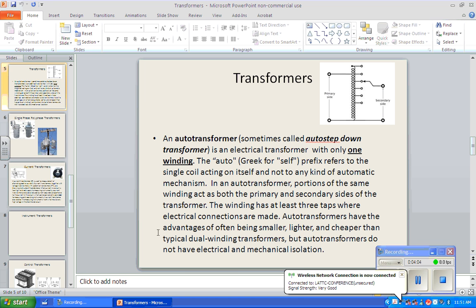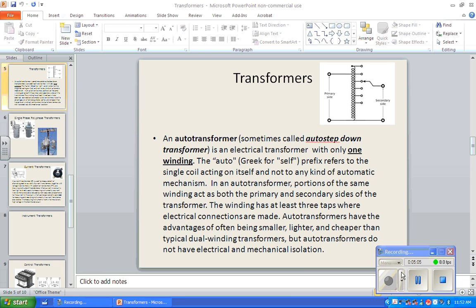Places where you will see in your future an auto transformer is at, for instance, the runway lights at an airport, or the taxiway lights at an airport. They're supplied by a constant current transformer. How do they keep the current constant? With an auto transformer, and it's got a floating coil to make everything stay the same. Why is that? Because we want the same exact brightness from them all the time. So what happens with those is if you break the light by running over it with an aircraft, it's got a built-in device that shorts the 2 connections together so the circuit stays on. And I can't think of what that device is called at the moment, but that's neither here nor there. Okay, so an autotransformer is a device where the two windings are tied together somewhere.